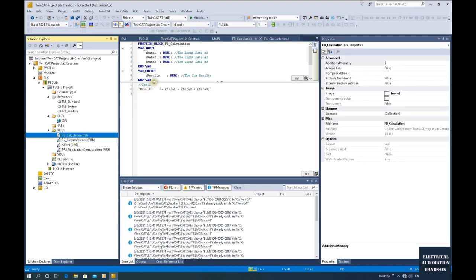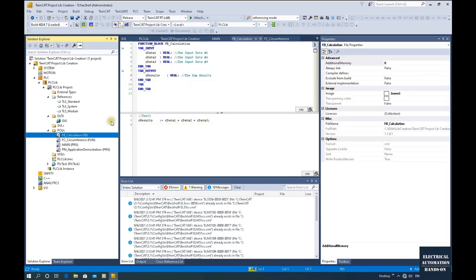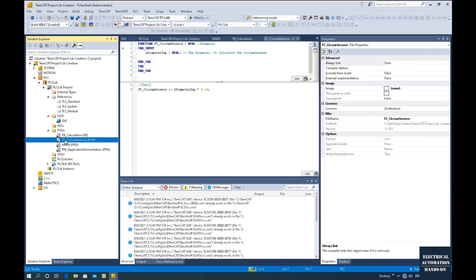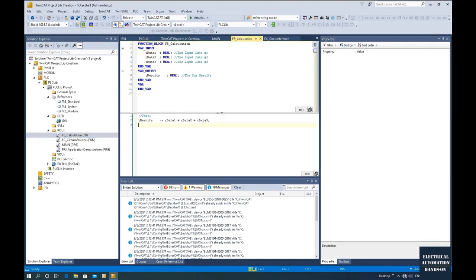In this project, for example, I created one function block and one function. The function block I named 'fb_underscore_calculation' — this is just a demonstration summing data one, two, and three equal to a result. And the function is a simple equation using the diameter to calculate the circumference of a circle. I highly recommend before you export your function block or function, you write comments on those inputs or outputs — try your best to write as much as possible. When we import this library, those comments help us to know the role of those inputs.